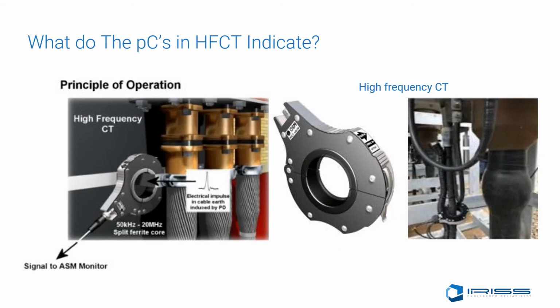PD pulses are easy to measure using the Sonus PD Pro or the Sonus PDX while in the HFCT mode. The HFCT clamp is a high-frequency current transducer which is clamped around the ground of the component being tested. The severity of the PD is measured by measuring the burst intervals between the end of a burst and the beginning of the next burst.